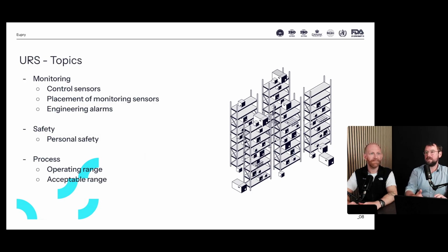So a good example of this would be cooling capacity. Let's say you have a cold storage, 2 to 8 degrees. You might have an engineering alarm that says now we are over 100% capacity on our HVAC system. But it would be much nicer to say we're at 85%, 86, 89, 95%, so that we're actually able to foresee this tendency before something actually happens. So engineering alarms is one of those really important topics that we see from an operational standpoint.